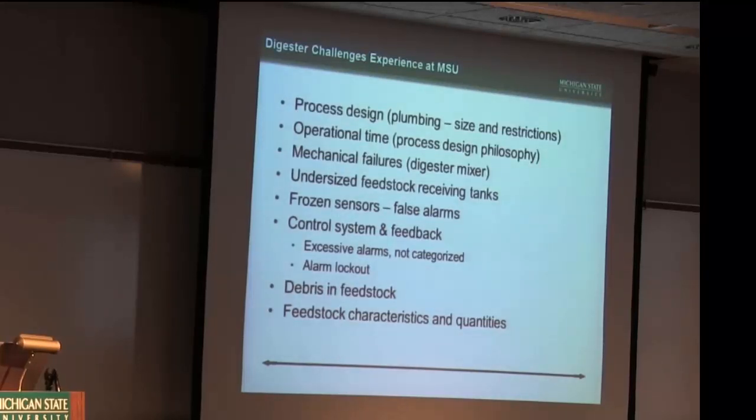And I think by the end of January, the changes will be done so that operator time is about 4 hours a day. We've had a mixer that continues to fail. We have two mixers in our big tank, our 400,000-gallon tank. We operated about 4 months of the year with both of those running, and then 8 months we were operating on just one mixer. And that does have an impact on performance.